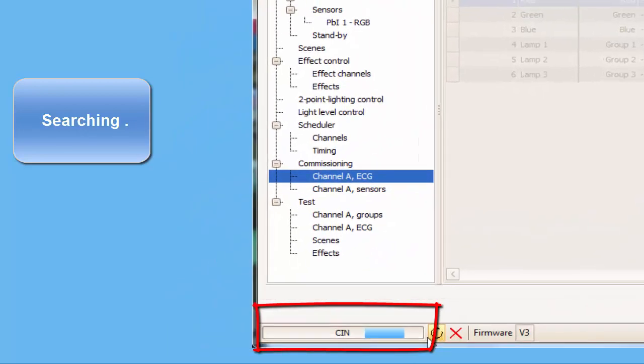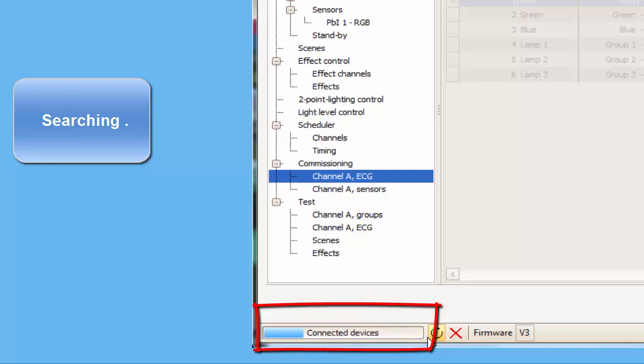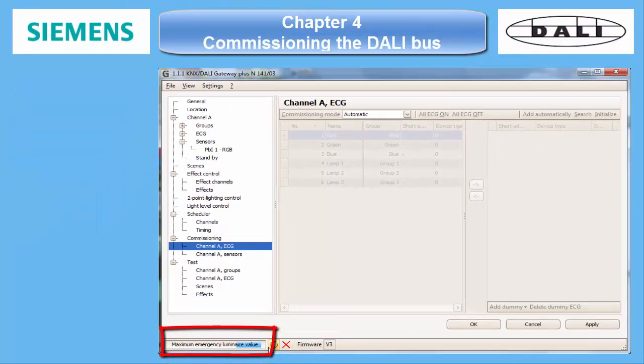The procedure which has happened in the background: at first, the DALI bus is scanned for valid short addresses on ECGs. If some are found, they are checked if they are unique. Then all other ECGs are triggered to randomize a long address, which is required to assign a short address in turn. If colliding addresses are detected, the program tries to resolve the problem by running a second randomizing pass.